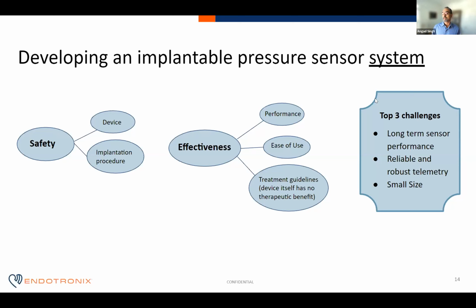Then effectiveness, the things that matter there are performance, particularly long-term performance. We're not monitoring an acute disease, it's a chronic disease. The device has to perform accurately for the life of the patient. So typical testing times for the devices are on the order of 10 years, a period over which you have to prove performance. The other important aspect is ease of use. Patient adherence is extremely important. If the patient is not taking these measurements on a daily basis or on a frequent basis, then you can't act on the information. So really, that has to become a big part of your development effort. How do you get to a form factor, a usability scenario that's actually going to promote patient engagement in the technology?